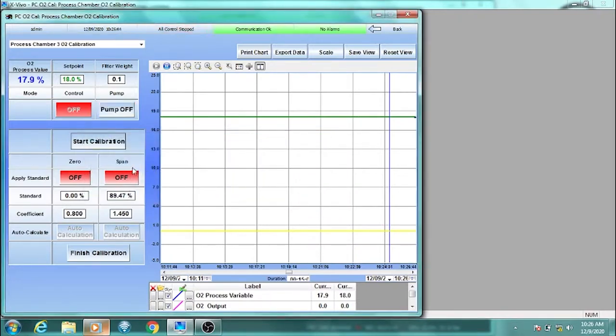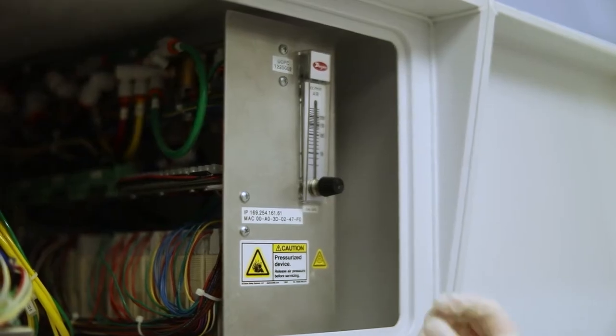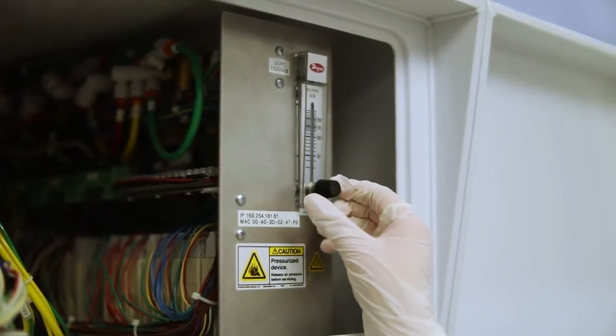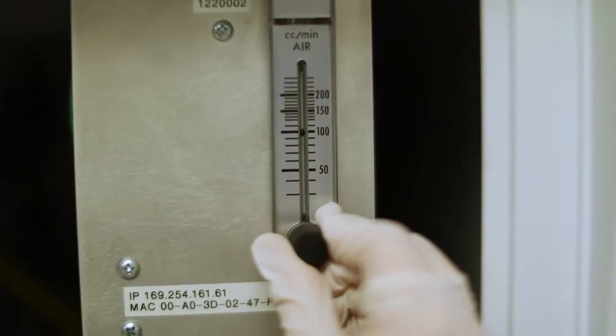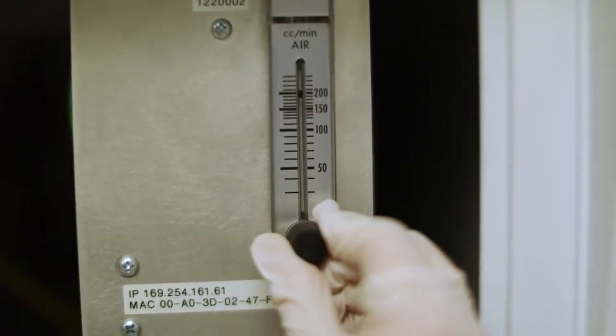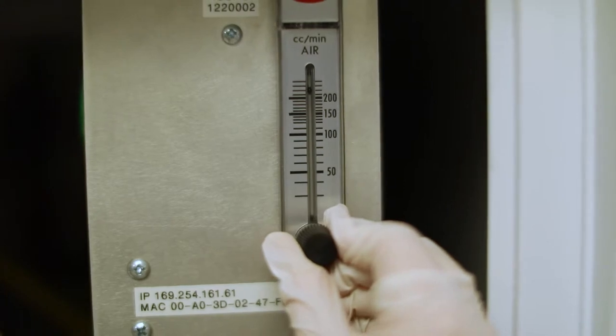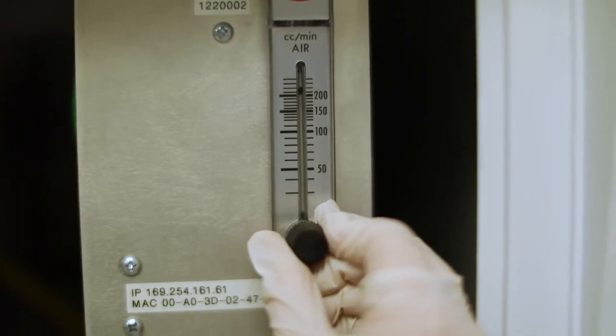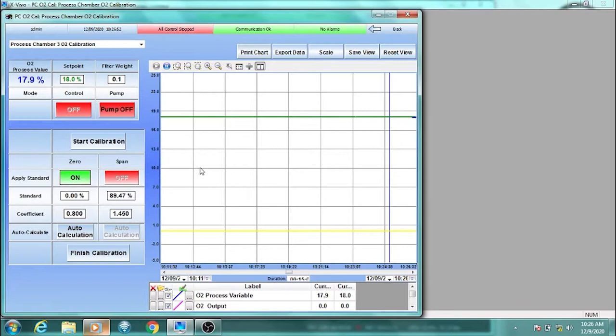Click OK. Turn the zero calibration on. Check the flow meter for the module you are calibrating in, usually located behind the enclosure panel that's above that module. It should read around 200 cc per minute, so adjust it if needed. For the zero calibration, nitrogen is passed by the sensor and should bring the reading of the sensor close to 0%. Wait a few minutes for the reading to level out and ensure it is within plus or minus 0.1 of 0%.